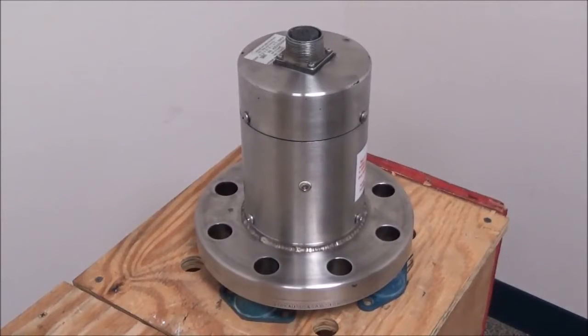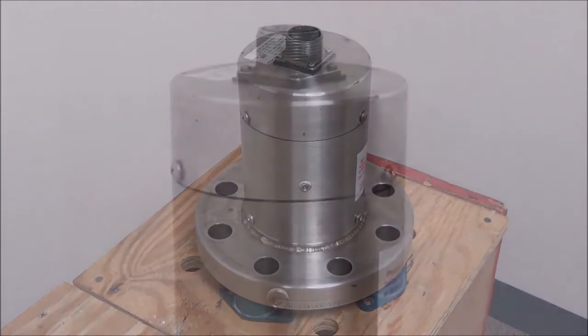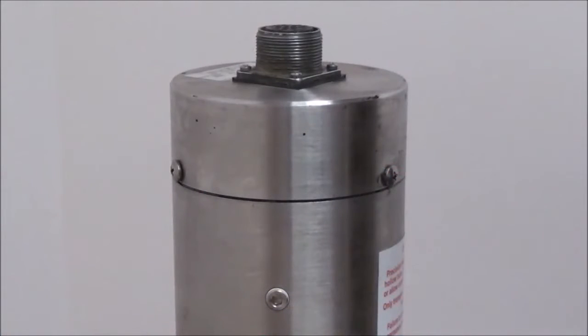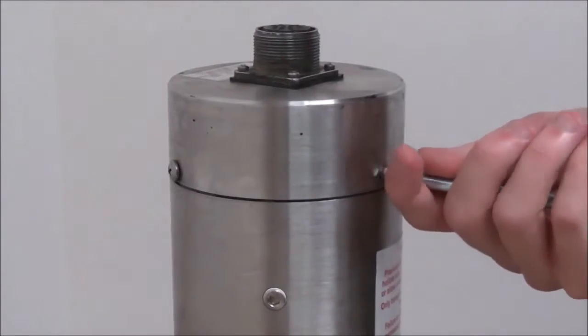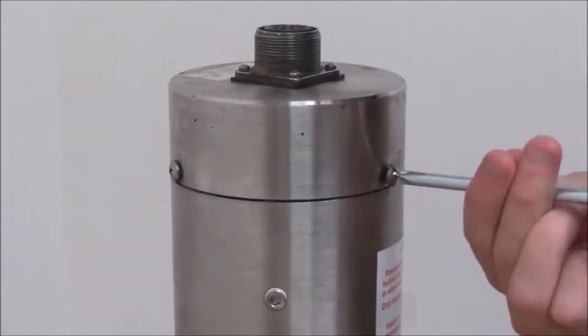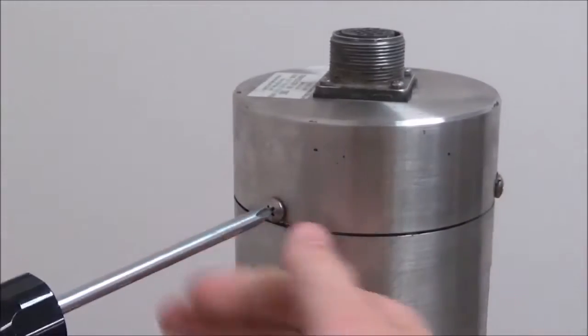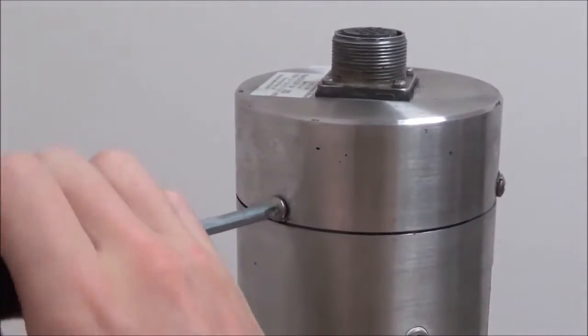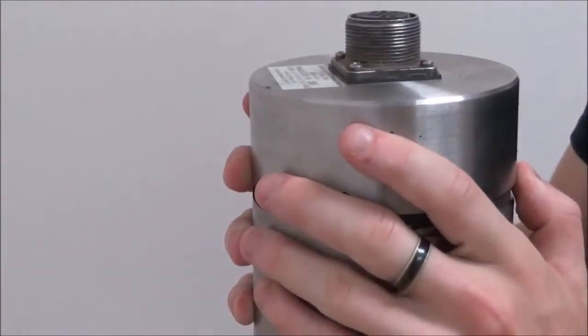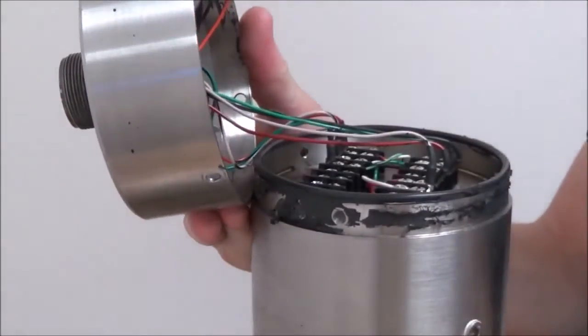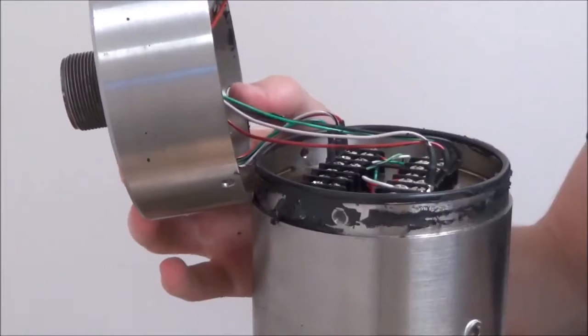Oh no! Your Nemetra viscometer came without a block RTD. No worries, with this tutorial you'll have your machine up and running in no time. First, you must remove the top 3 screws that are attached to the transducer of the viscometer. Once all 3 screws have been removed, simply pop off the transducer to reveal the wiring below.